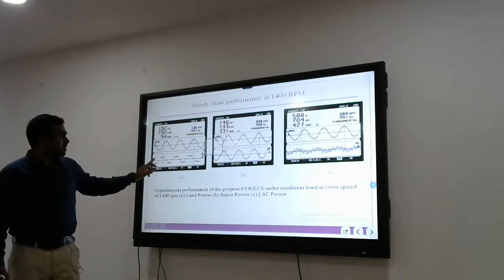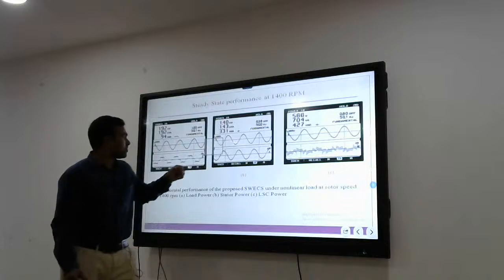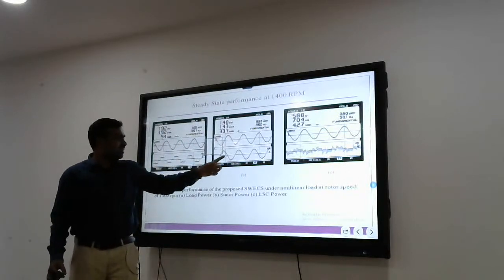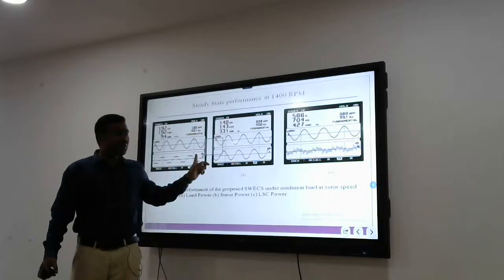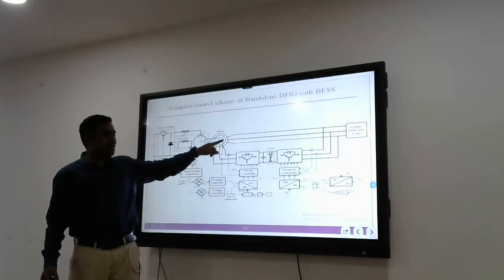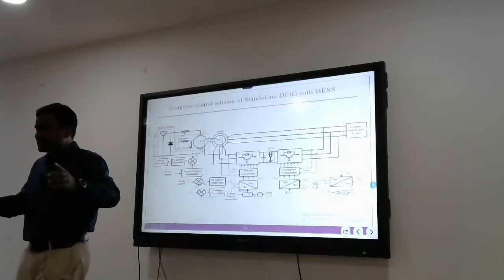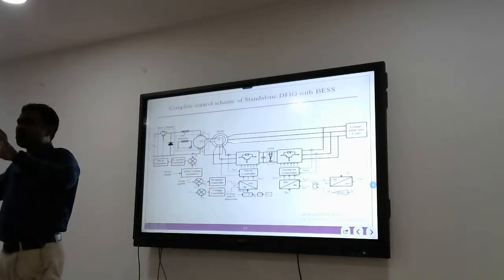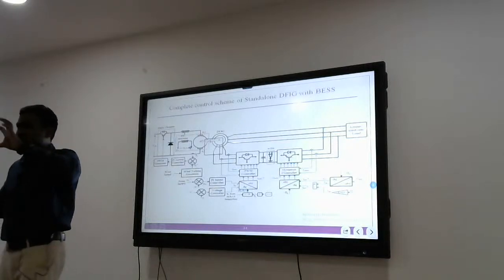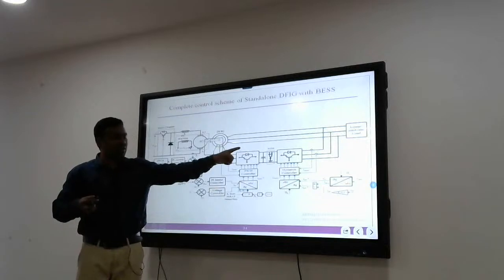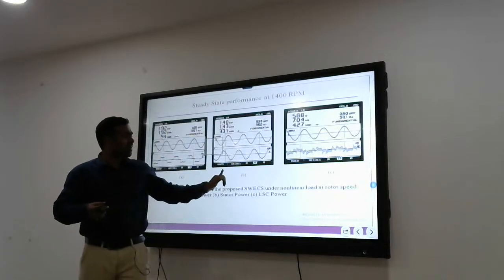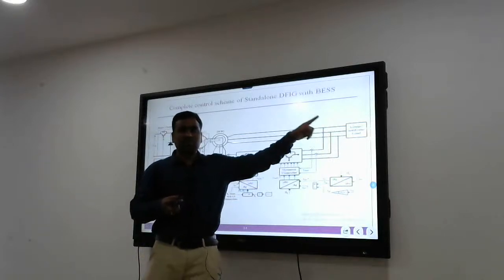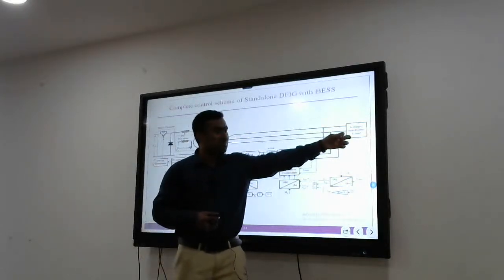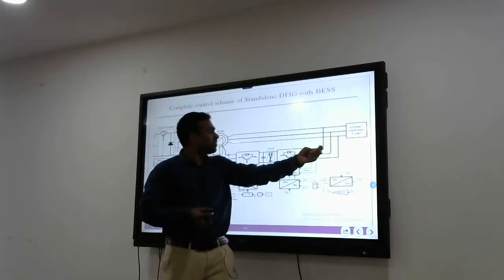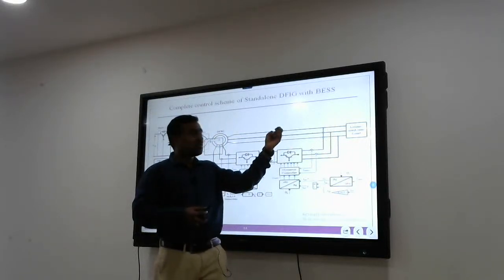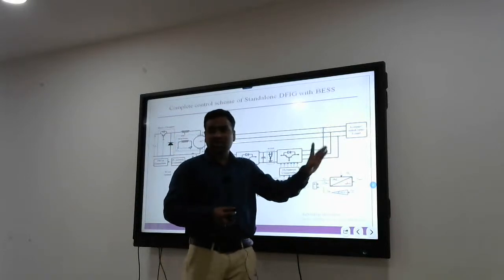These are the power results. If you see here, the load is non-linear, so the current is like this, but still my stator currents are very much sinusoidal. I have to maintain that, because if my current here is non-linear, it will have some harmonics, and in such a big machine, due to those harmonics, you will have harmonic torques and the machine may vibrate. So you should have sinusoidal currents here. The harmonic current will be supplied by this converter. Here you have very non-linear current, and here you are making it sinusoidal, and the harmonic part is supplied by this converter.